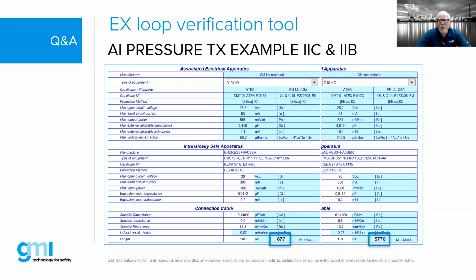If we look closely, the parameters on the right-hand column are actually for gas group 2B gases, while the ones on the left-hand side are for 2C gases. 2C gases, such as acetylene and hydrogen, have very low minimum ignition energy curves, meaning it doesn't take much to ignite them, whereas 2B gases typically require a higher level of energy.